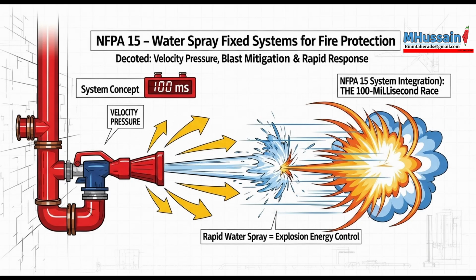NFPA 15 forces you to calculate and include PV unless it works out to be less than 5% of the total pressure at that specific junction point. It's 8.1.5. And Annex A.8.5.1.2 gives a stark warning. Ignore PV in high-velocity situations, and your final design might actually need over 26% more pressure at the source than you initially calculated just to get the required flow. Wow, 26%. That's a massive potential failure in the design.